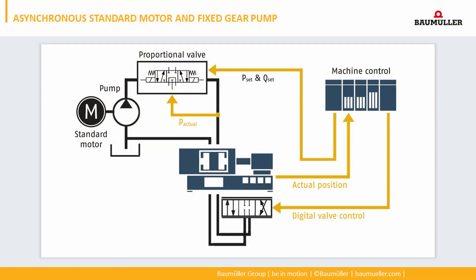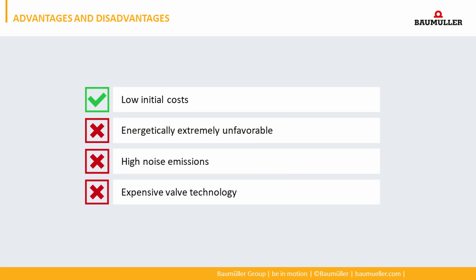The first system consists of a standard induction motor which runs directly on mains and therefore with a constant speed. The pump is an internal gear pump with fixed displacement, meaning the pump delivers permanently a constant flow rate, no matter if this is currently needed on the machine or not. The machine control sends pressure and volume set values to proportional valves, which then control the hydraulic pressure and flow rate. The only advantage of this system is its low initial cost, but there are several disadvantages: high energy consumption, high noise emission and expensive valve technology.